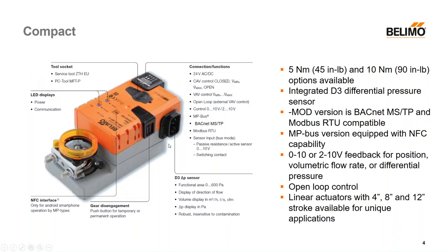Starting with the existing products, we have the compact line. This product line is named because the integrated pressure sensor makes it a more compact solution than having two separate products — the actuator and the differential pressure sensor. It's available in 45 inch-pound and 90 inch-pound sizes, or 5 and 10 newton meters. It has an integrated D3 differential pressure sensor. The D means differential pressure sensor and the 3 means it's Belimo's third iteration, which has made tremendous improvements versus the last iteration, mainly being much more resistant to dust and other contaminations.